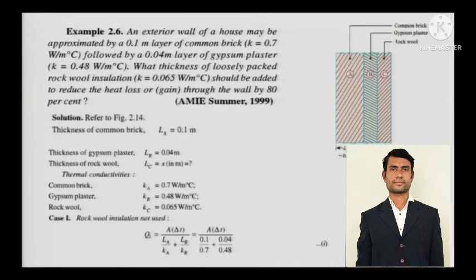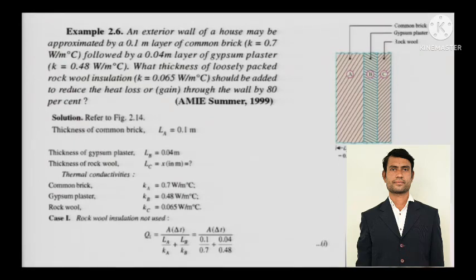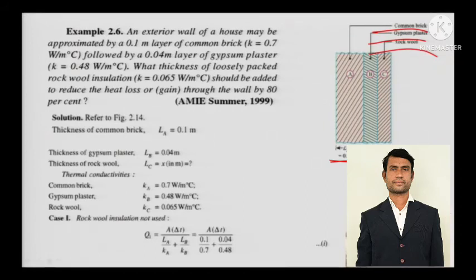Now we move to three layers of a composite wall. An exterior wall of a house may be approximated by a 0.1 meter layer of common brick (K equals 0.7 watts per meter degree Celsius) followed by a 0.04 meter layer of gypsum plaster. What thickness of loosely packed rock wool insulation should be added to reduce the heat loss or gain through the wall by 80%? The K value for rock wool is already given.